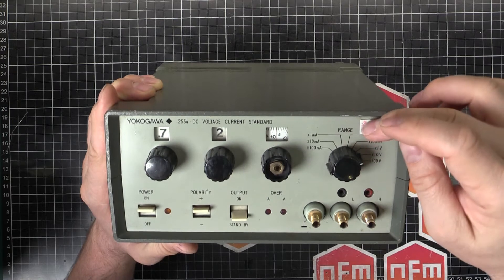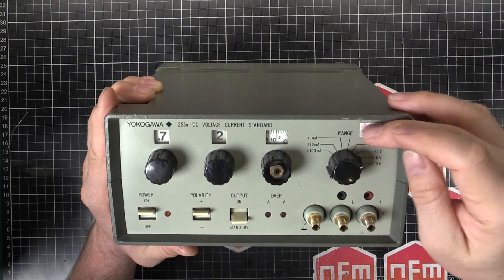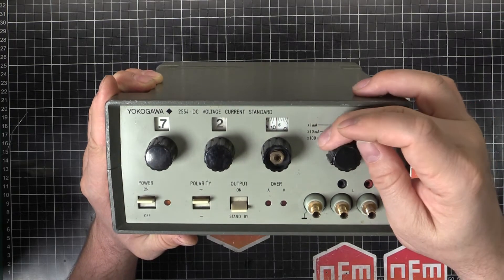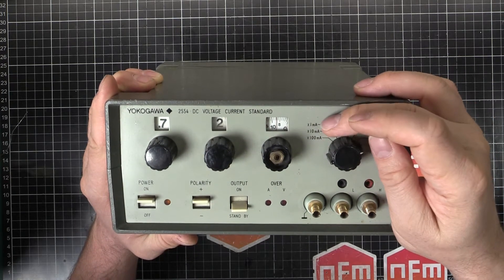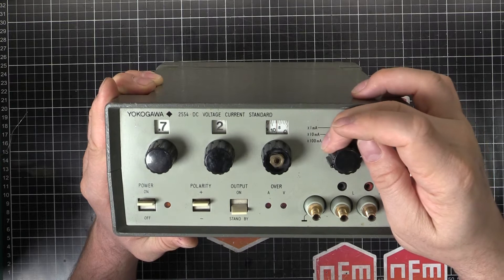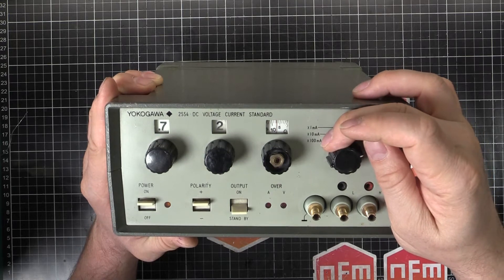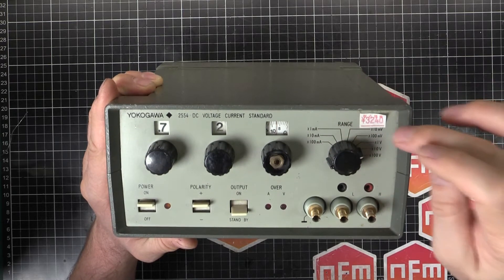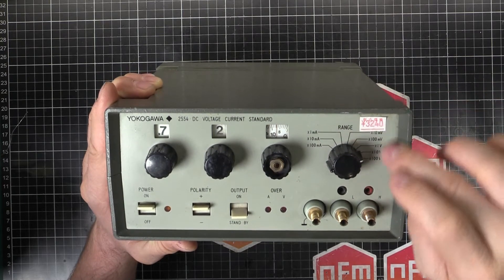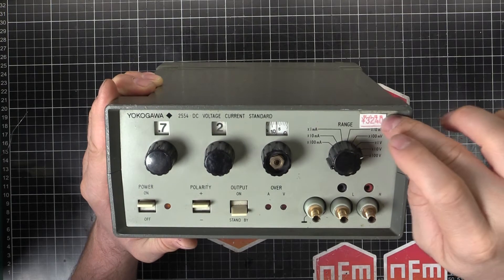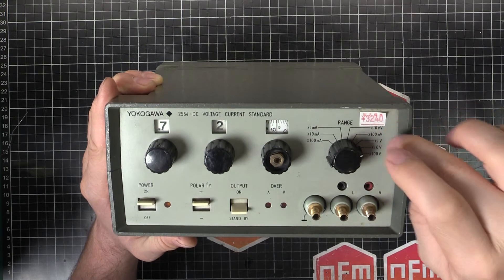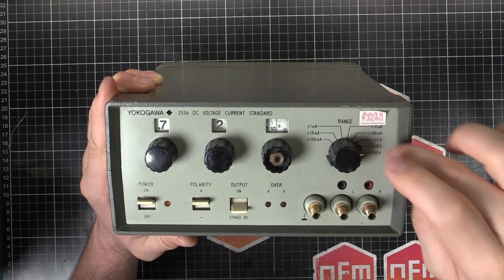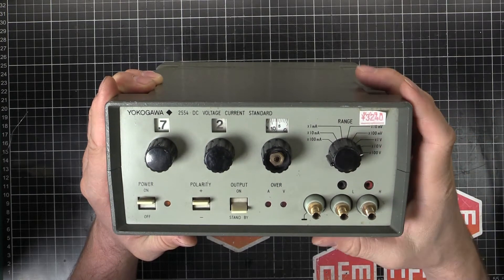So we've got two sides of the range switch. We got 1 milliamp to 100 milliamps - 1 milliamp, 10 milliamp, 100 milliamp for the current output ranges and the voltage ranges 10 millivolts to 100 volts. We've got 10 millivolts, 100 millivolts, 1 volt, 10 volt and 100 volts.